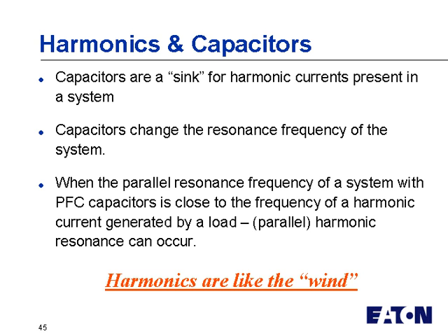But as you look at that, without the wind, there would be no resonance in that bridge, because as every structure, electrical or mechanical, has a resonant point, if you don't excite that resonant point, you don't need to worry about it. But with harmonics, capacitors are typically a sink for harmonic currents in the system, but they also change the resonant frequency of the system, and that's why we're concerned when we put capacitors on. And if the parallel resonant frequency when you put a capacitor on the system is close to a harmonic generated by a load like a drive or computer loads, for example, harmonic resonance can occur. And again, harmonics are like the wind in this example. They excite the resonance of the system. Capacitors that have been on a system for years may not have any problems until you add harmonic sources to the system, and that's why we're so concerned today.